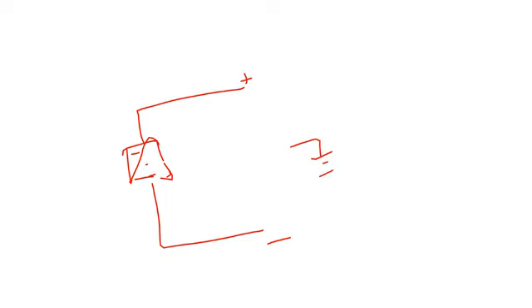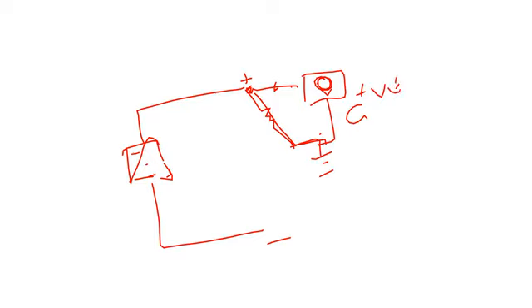Remember, if you have a positive ground fault, then if you measure with a Fluke, there's our voltmeter, between positive and ground, you will see 0 volts. So whichever pole has 0 volts or the least amount of volts is the pole that has the ground. This can sometimes confuse people. They think the one with the highest voltage is the one with the ground. That's not the case, because if you have a ground fault, you've basically got a short circuit between the ground terminal and the positive terminal, and there will be no potential there. So if you have no potential between positive and ground, then you have a positive ground fault.